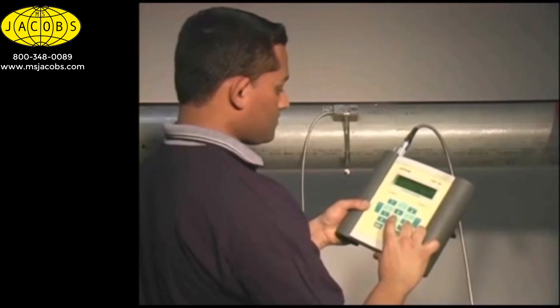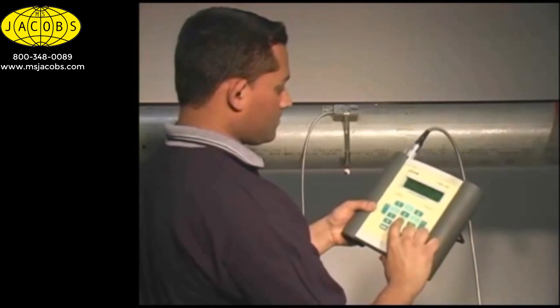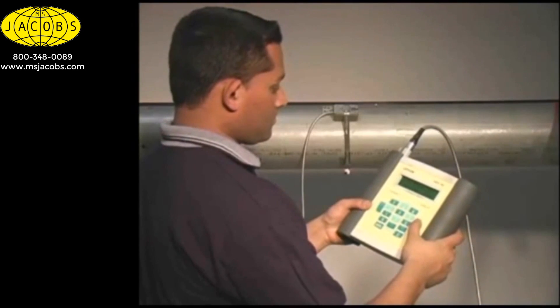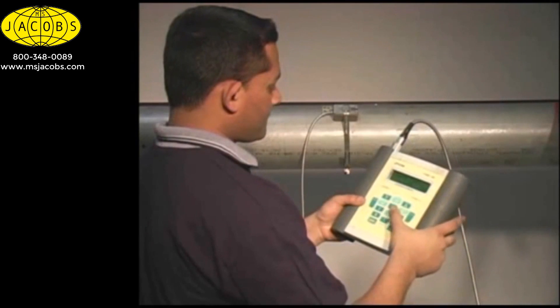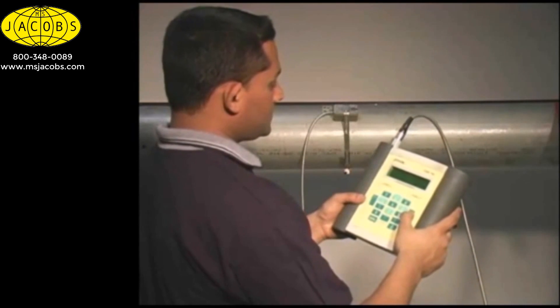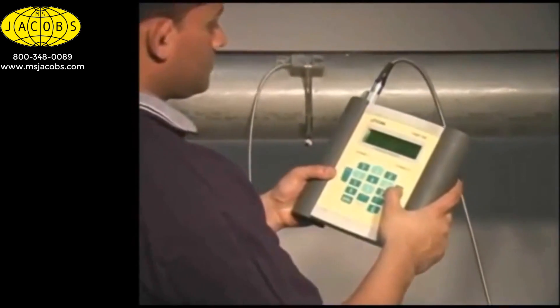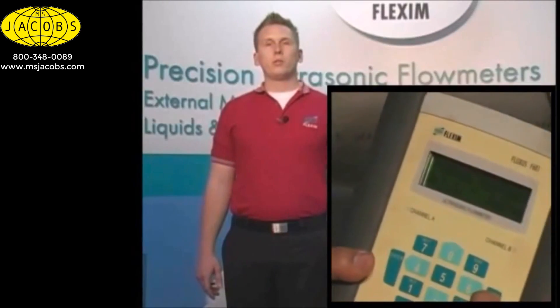Now that we have our first transducer mounted, we go to the meter and program in all the necessary pipe parameters. When we get to the signal strength screen, we are given a recommended distance to mount our transducers at for our particular application. For details of how to program FLEXIM flow transmitters, please watch videos 1, 2, or 3.